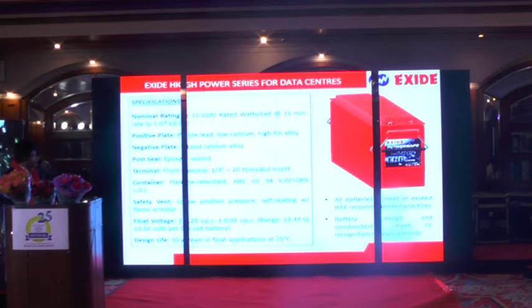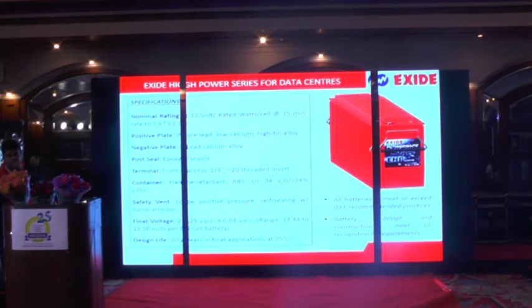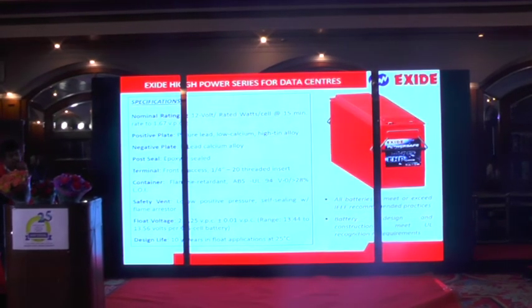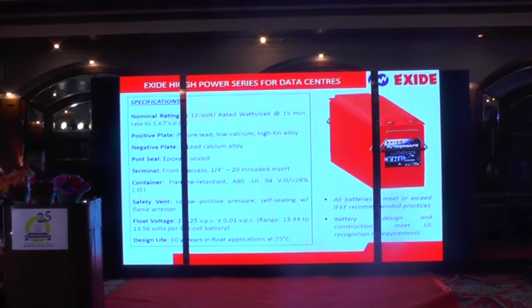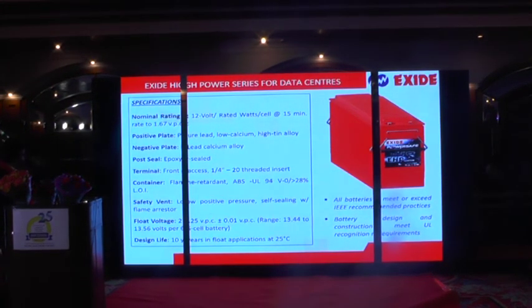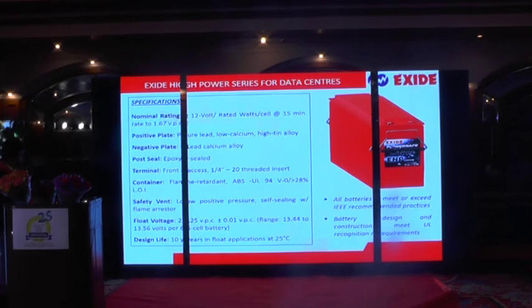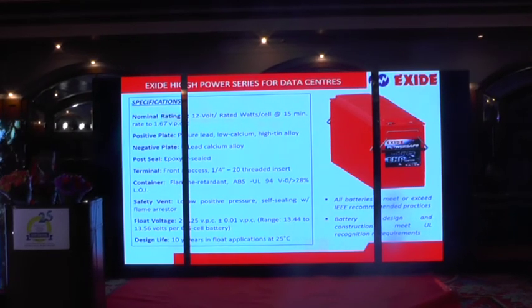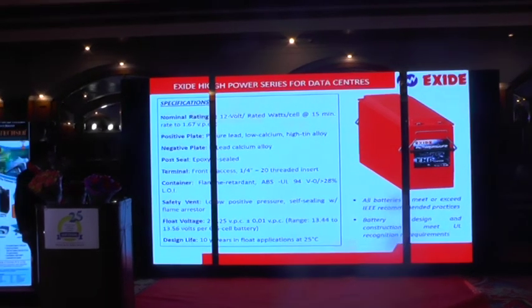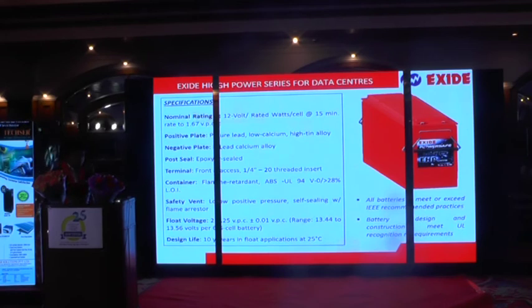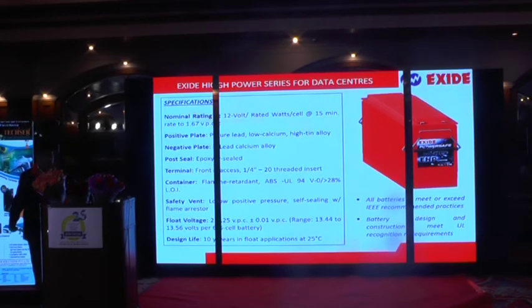These are the specifications. These batteries are not rated as an ampere hour. There is no ampere hour rating. These are rated at a power rating, meaning wattage rating. So when we say a 750 watt battery, what does it mean? It means that if I discharge the battery at that rated watts up to 1.67 volts per cell, it will give a minimum backup of 15 minutes. So it is like our conventional VRLA product.